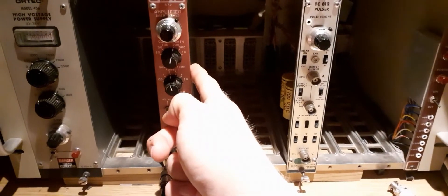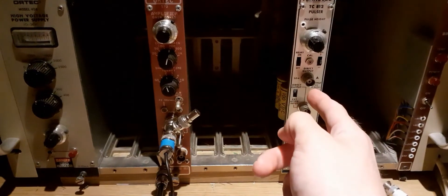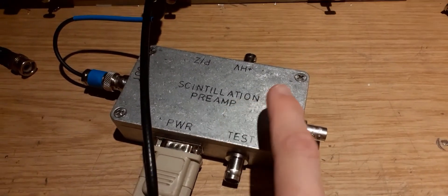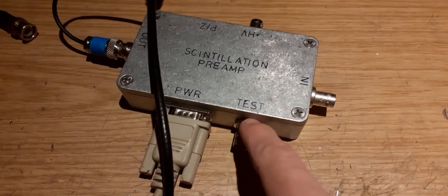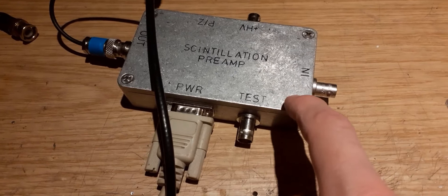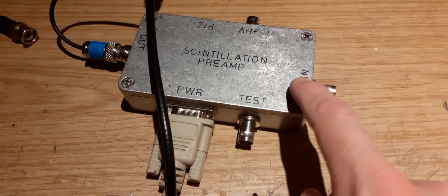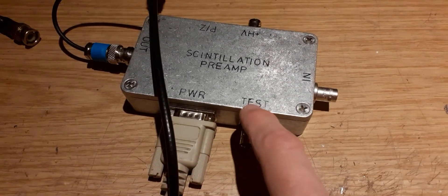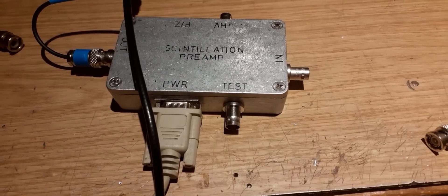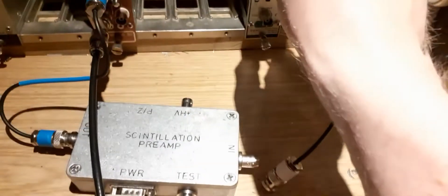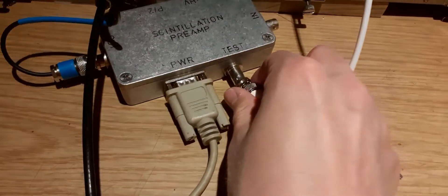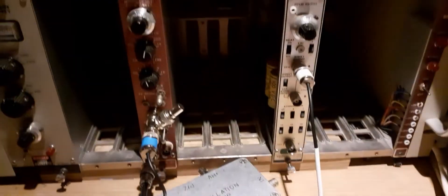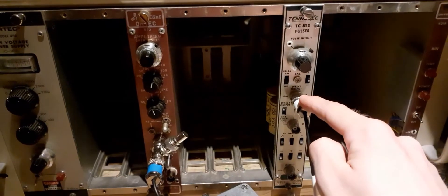Here we are. This is a very minimal NIM bin—it just has a spectroscopy amplifier and the pulser. Then I have a preamp here which is the preamp I would normally use with my scintillation counter seen here. I've made a test input on this—I've built this myself—and the test input just feeds into the same amplifier but through a very small capacitor, and that works quite well. So let's hook it up. We just take the direct output here and feed it to the test input.